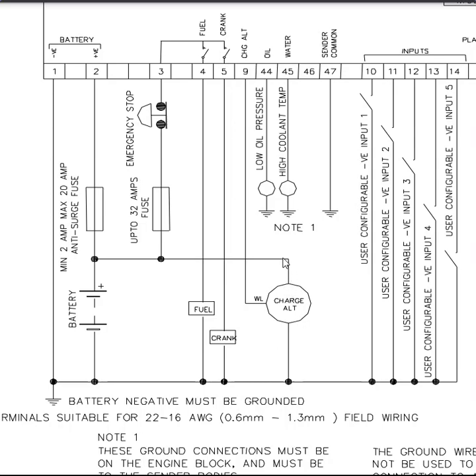Also, you're going to have the charging from your alternator, not the D+, but the other connection which will charge the battery. That's already going to be done. So now we see number 3, which is the e-stop. We are going to have voltage going through the e-stop when everything is working normally. When you try and start the gen, number 3 is going to feed voltage to 4 and 5, closing the fuel relay and the crank relay.